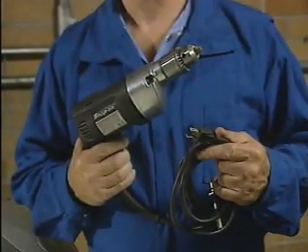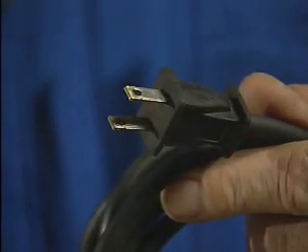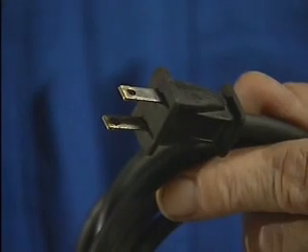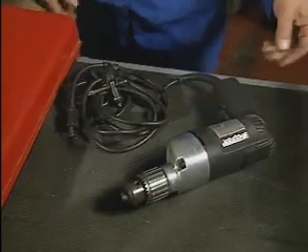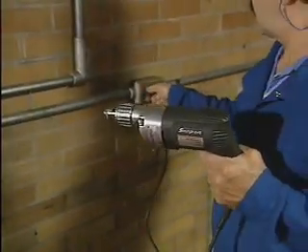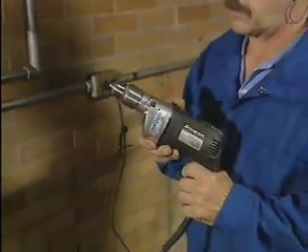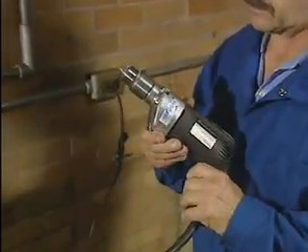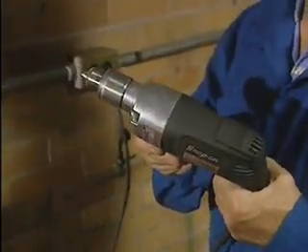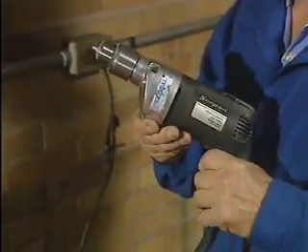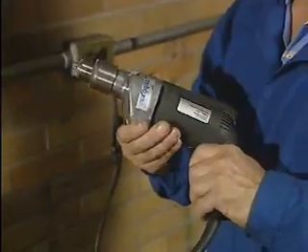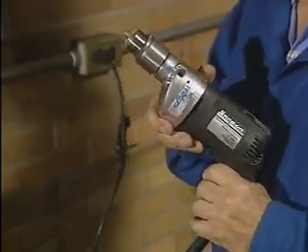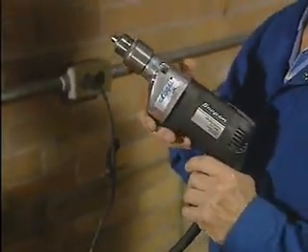If an electrical tool is double insulated, it does not have to have a ground conductor in its power cord. Double insulated tools have plastic casings that insulate the user from any fault inside the tool. If the casing is in good condition, there is little danger of shock. One word of caution is advisable, though. Not all plastic-coated tools are double insulated.